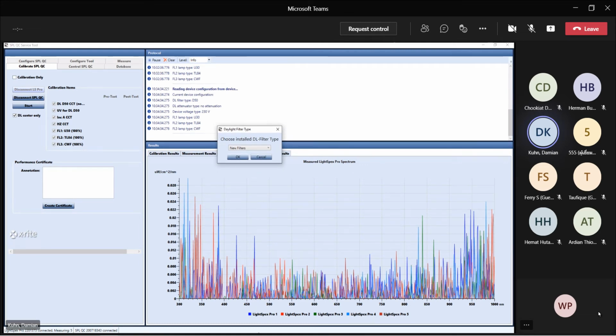So here, this is where you select if your instrument is installed with new or old daylight filters. As I said, if you have any device that is older than 2019 or so, typically you would select the old filters here. If you have a newer device, then you would typically select new filters. As I said, if you're unsure, you go with the option you believe fits best to the instrument. Worst case, you would actually have to recalibrate daylight afterwards and make the setting to the other setting than what you were using at your first attempt.